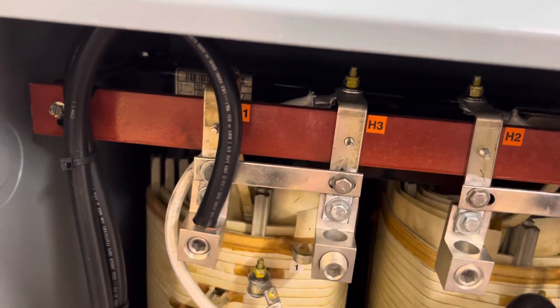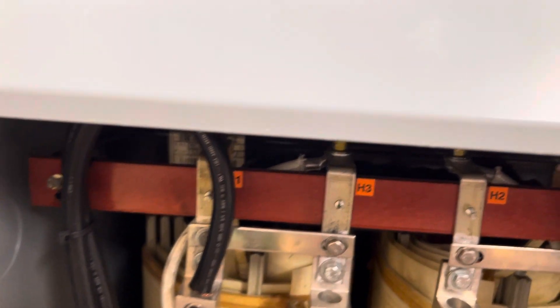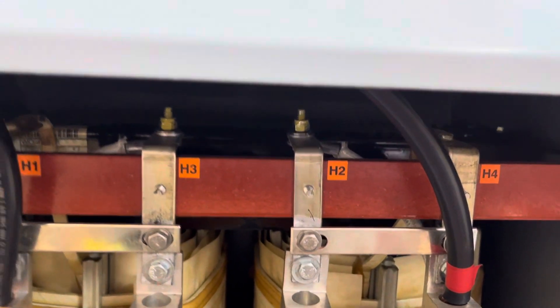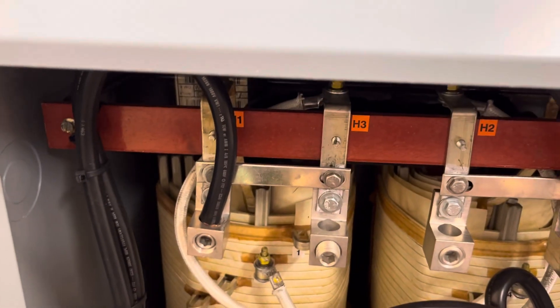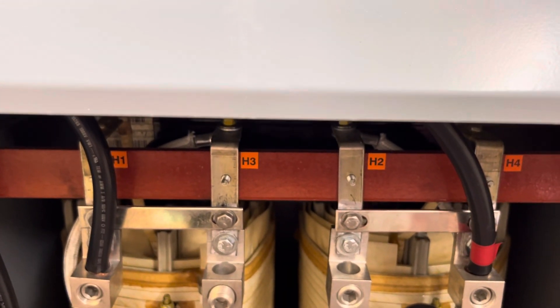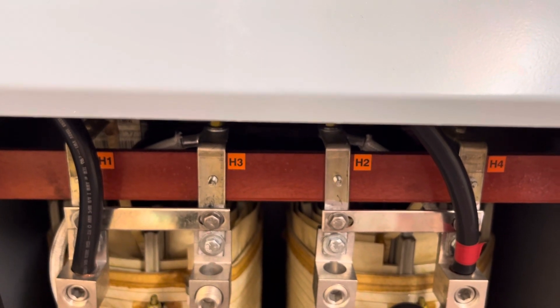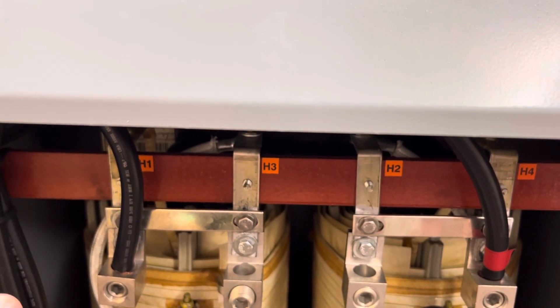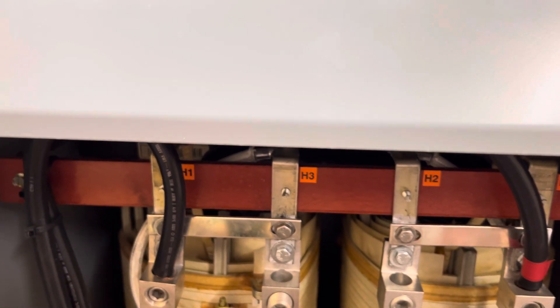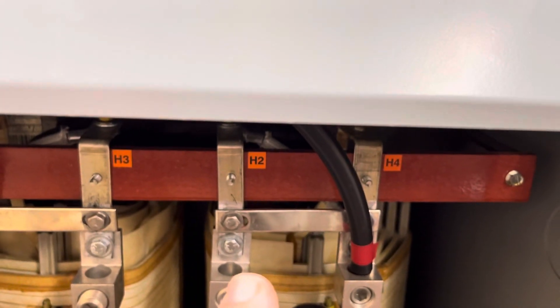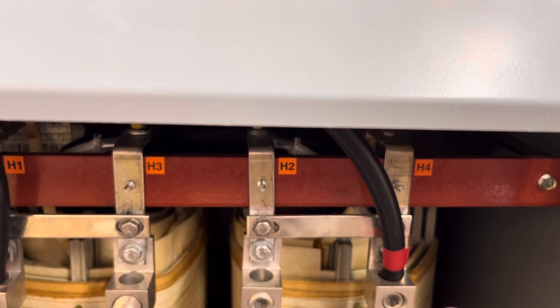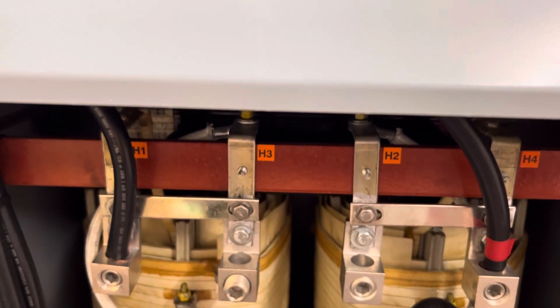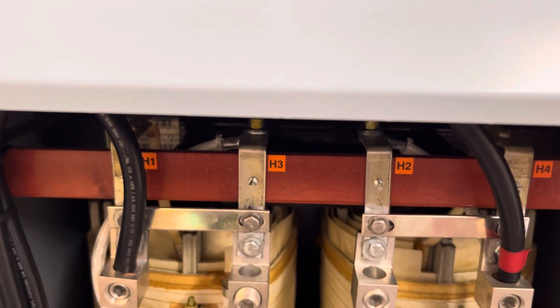This is H1 and H3, H2 and H4, H1, H2 being one winding, H3, H4 being the second winding. So if I connect H1 and H3 together with this bus bar, and I connect H2 and H4 together in this bus bar, then I'm paralleling the primary winding. I'm putting in 240 volts.